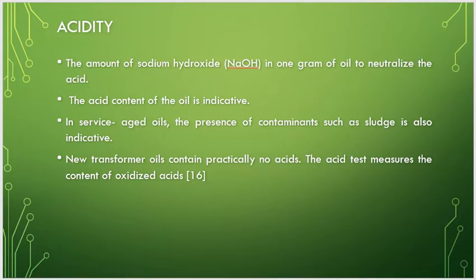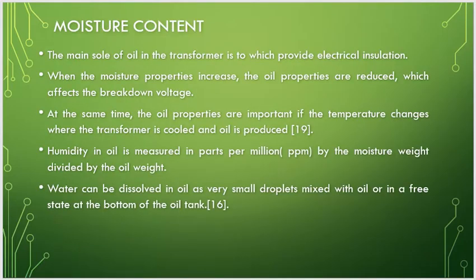The acid content of oil is indicative. In oil, the presence of contaminants such as sludge is also indicative. The transformer oil should contain practically no acid. The acid test measures the content of oxidized acid. Then for moisture content, the main role of oil in the transformer is to provide electrical insulation. When the moisture content increases, the oil properties are reduced, which affects the breakdown voltage. At the same time, the oil properties are important if the temperature changes when the transformer is cooled. Humidity in the oil is measured in parts per million, ppm, by the moisture weight divided by the oil weight. Water can be dissolved in oil, as very small droplets mixed with oil, or in a free state at the bottom of the oil tank.